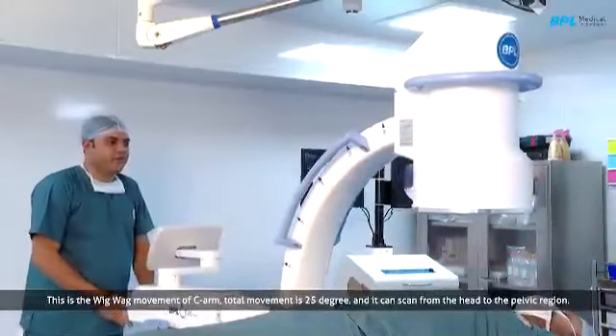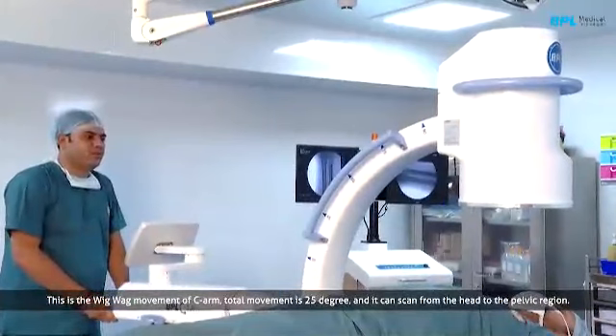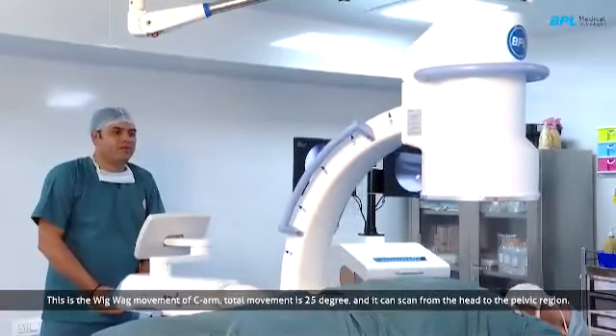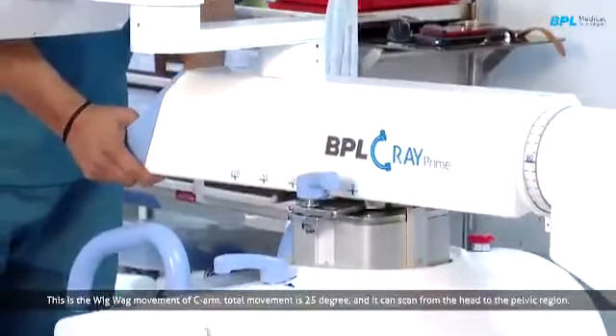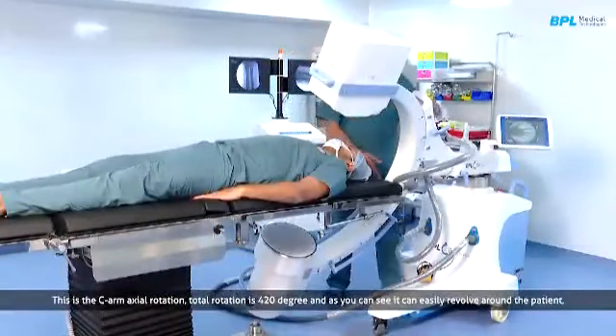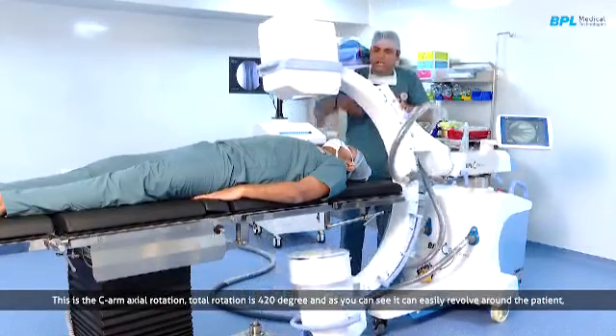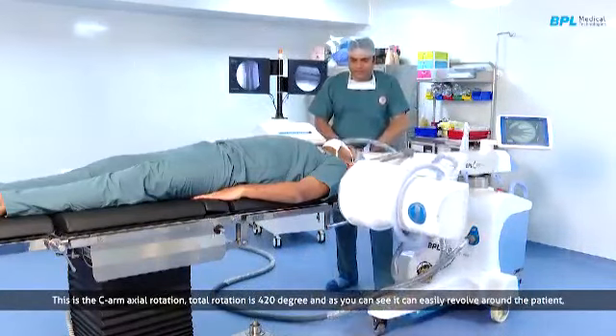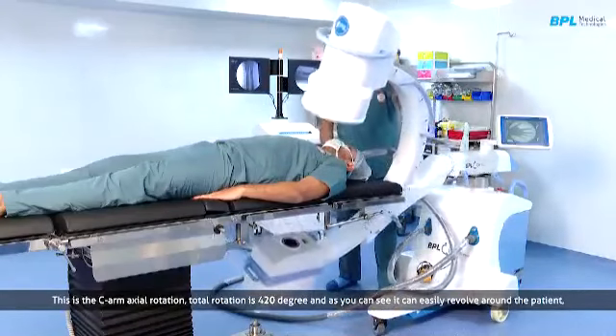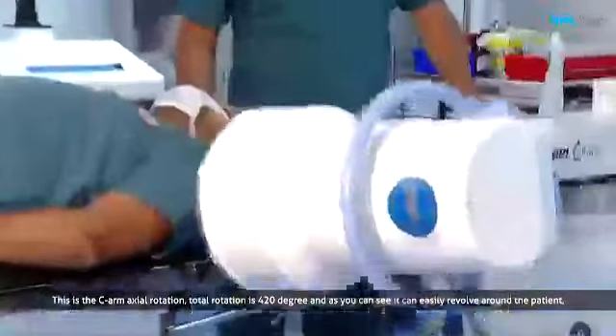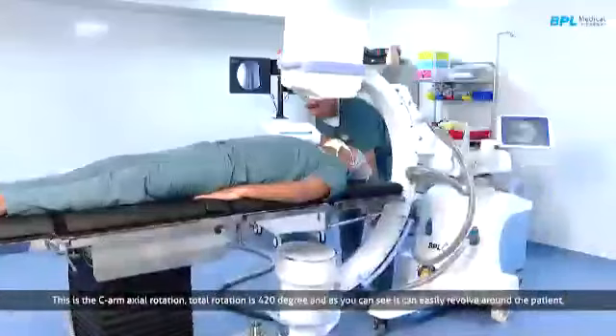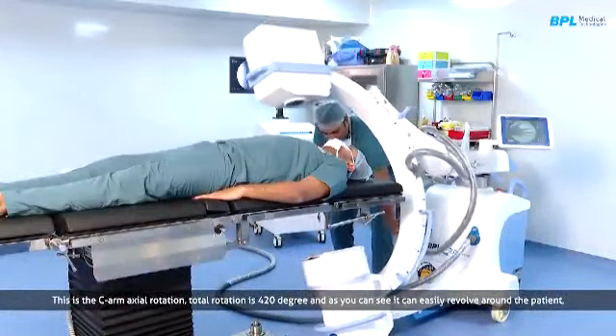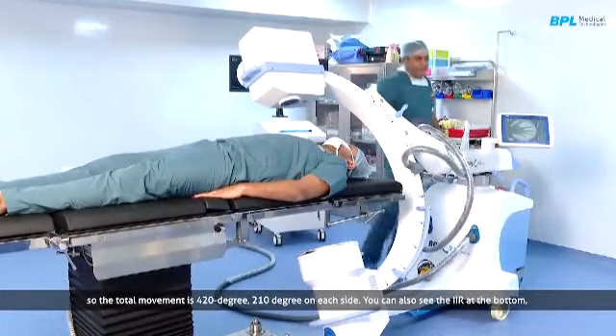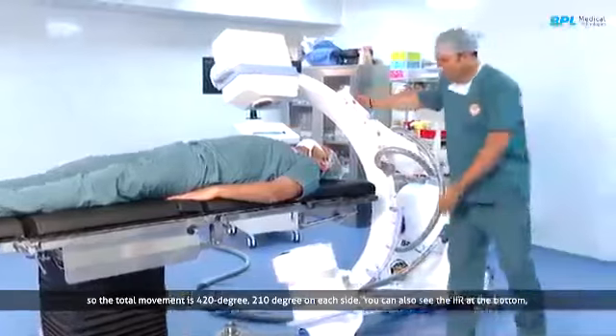This is the back and forth movement of C-arm. Total movement is 25 degree, and you can see it can scan from head to pelvic region. This is C-arm axial rotation. Total rotation is 420 degree, and you can see it can easily revolve around the patient. So total movement is 420 degree, 210 degree on each side, and you can see even the II at bottom side. This C is large C.